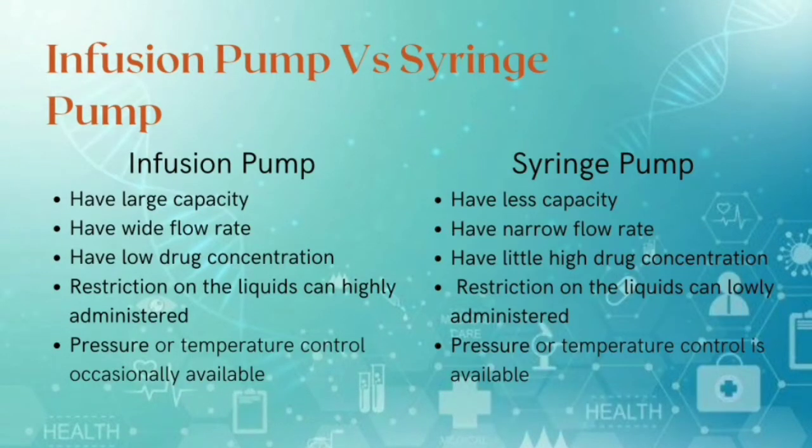If we compare syringe pump with infusion pump, syringe pump has less capacity and a narrow flow rate. And also, syringe pump has a slightly higher drug concentration than the infusion pump. The restriction on the liquids can be administered lower than the infusion pump. Pressure or temperature control is available in syringe pump, which is only occasionally available in infusion pump.